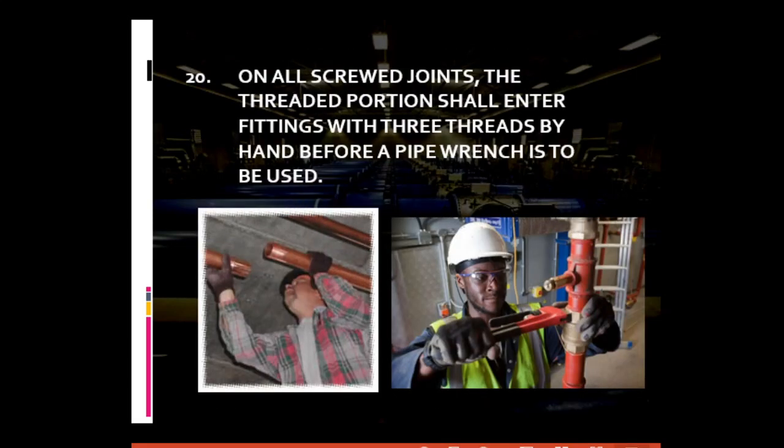For general piping requirement number twenty: on all screw joints, the threaded portion should enter fittings by three threads or three revolutions by hand before a pipe wrench is used. This is to prevent possible damage during the tightening of screwed joints or pipes. It is a standard procedure to manually enter at least three threads of the screwed pipe or joint by hand before making use of a pipe wrench — one thread being equivalent to one revolution.